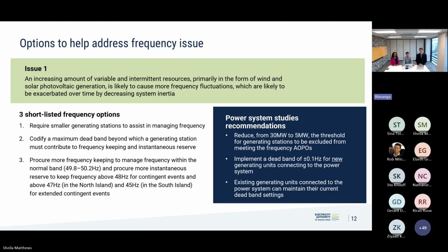So the authority at the time decided to do further work in this area, and now some years later we're at that point where we've done further studies. The system operator's recommendation is to go with a deadband of plus or minus 0.1 hertz for new generating units connecting to the system, and to leave any deadbands that existing generation has in place at the moment as is. On that, you'll see in the paper the authority is at the moment of the view that the deadband should probably be the greater of the 0.1 hertz recommendation from the system operator, or, if there's an inherent deadband in place because of the original equipment manufacturer's specification, you'd use that deadband instead. This is explained in the paper, and you'll see our thinking around that.